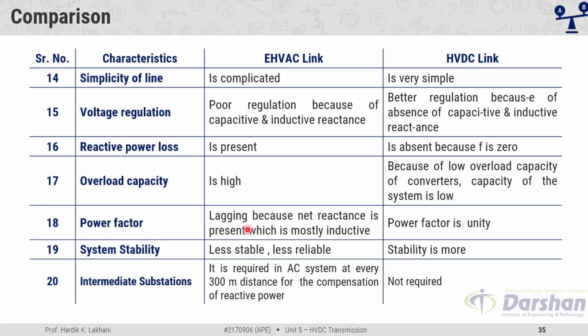The power factor of AC links is lagging because net reactance is mostly inductive, whereas the power factor of HVDC links is unity. Overall, AC links are less stable and less reliable, but DC links are more stable and more reliable. In AC links, an intermediate substation is required at every 300 km for reactive power compensation, but in DC there is no need for intermediate substations.